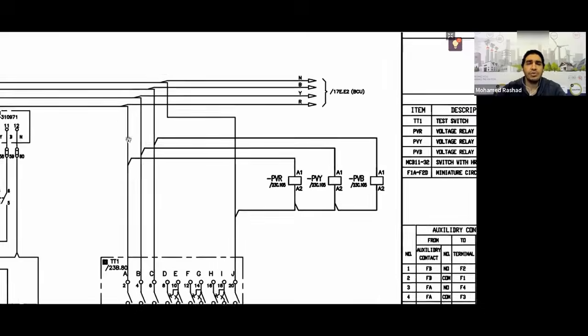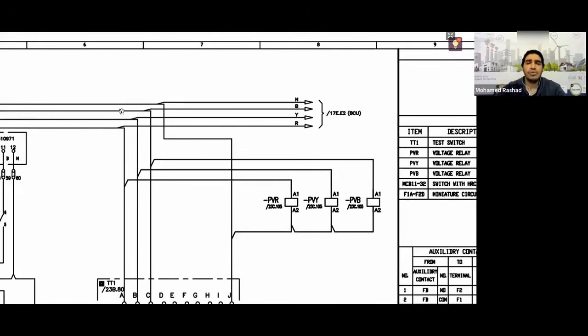The red, yellow, blue, and neutral operate the red with the neutral on an auxiliary relay, the yellow with the neutral on an auxiliary relay, and the blue with the neutral on an auxiliary relay. 3 auxiliary relays operating with AC voltage. These are 3 auxiliary relays that operate with AC voltage, not DC, AC voltage. These 3 are now connected to the VT voltage. So now, if this VT is actually reading a real voltage, then these 3 auxiliary relays should be energized.